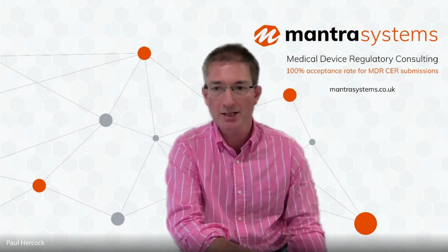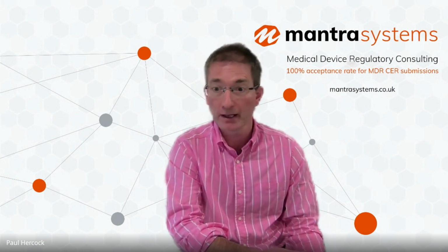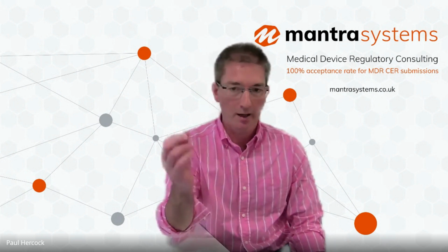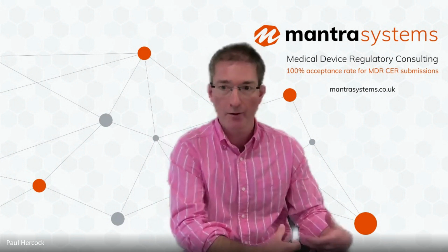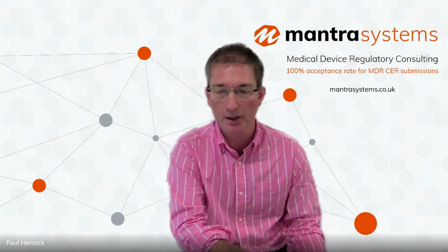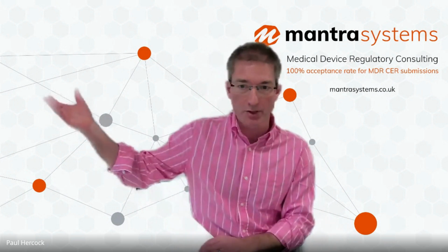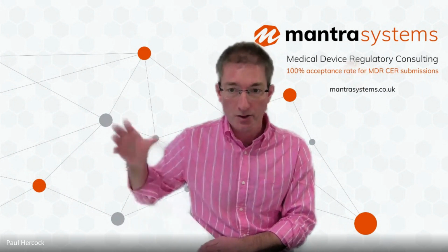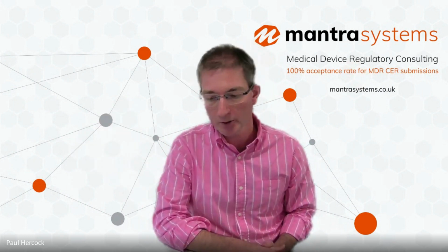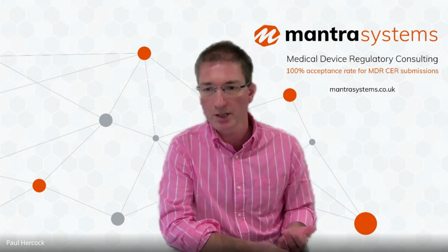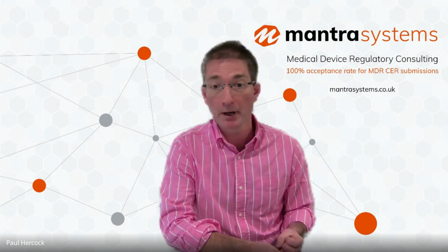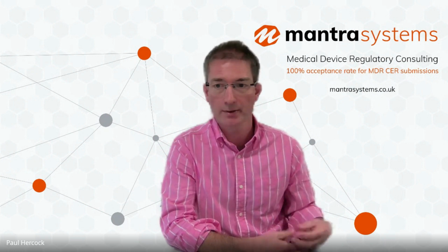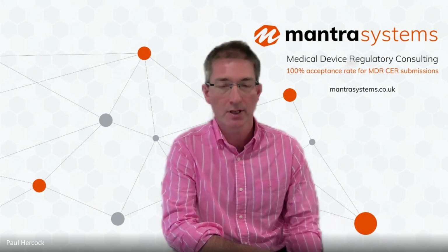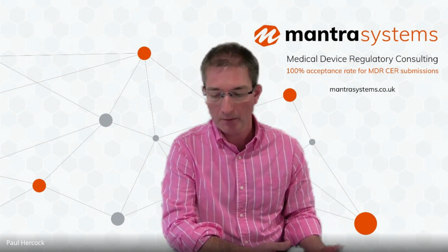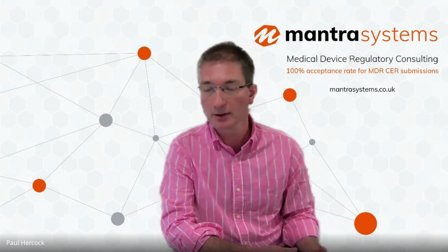So again, if you go back to a gas tap, that doesn't have any direct clinical benefit. It doesn't do anything unless it's attached to a delivery pipe and an oxygen mask, and the patient needs it and it's been prescribed appropriately. There are so many steps between the gas tap, which is an inert piece of apparatus that doesn't actually do a lot on its own from a clinical perspective. So probably the risk analysis will be mostly in relation to non-clinical risks. Again, to extrapolate this example, perhaps the risk of fire would be a risk. And then the benefits would similarly be technical.